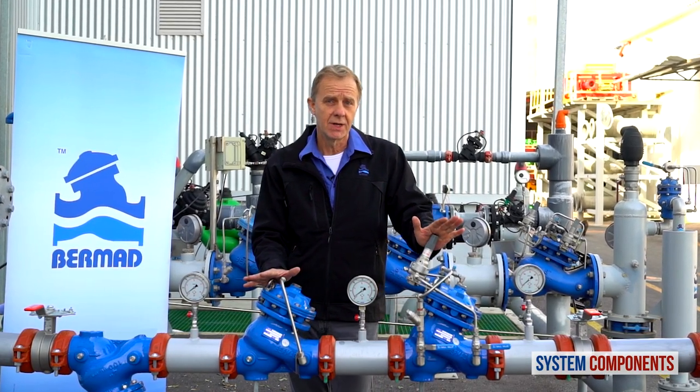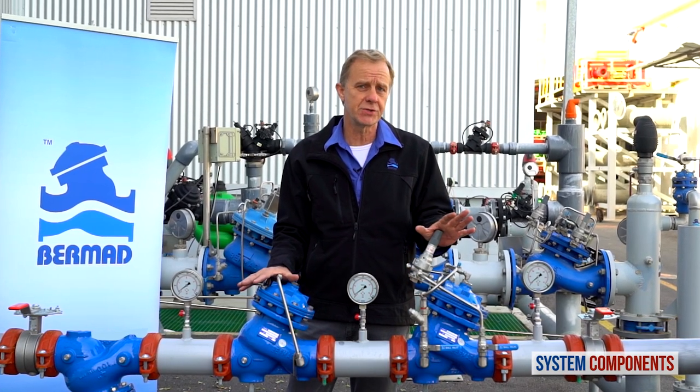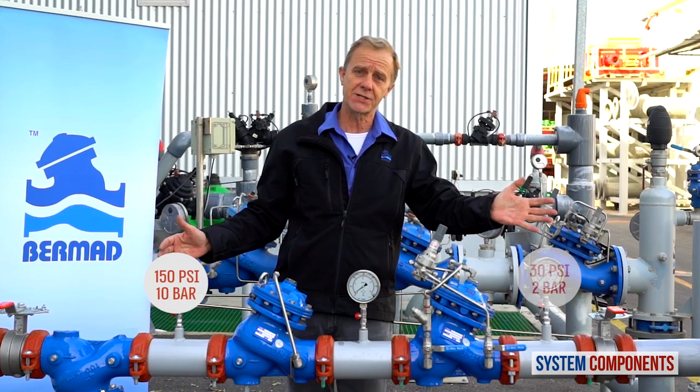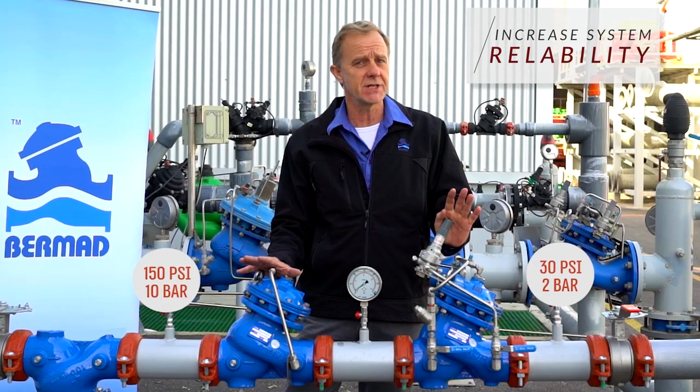So as you can see in this example, by using two pressure reducing valves, we are able to significantly reduce the pressure across the station from 10 bars at the inlet to 2 bars at the outlet, dividing the load with two valves and thereby increasing reliability and service life.